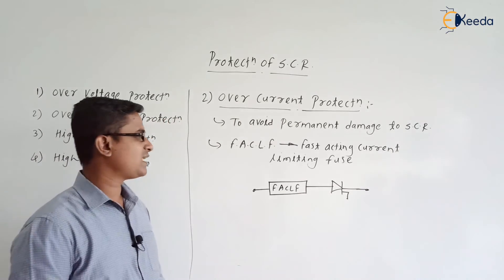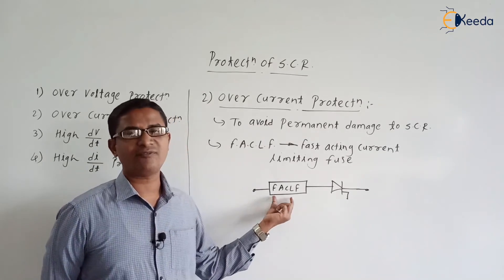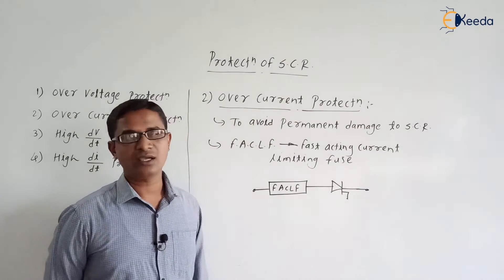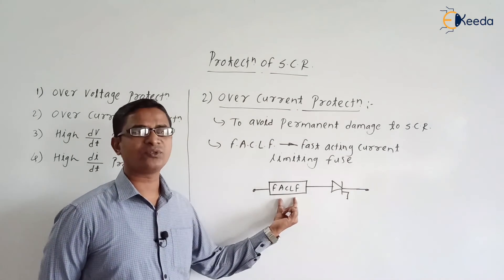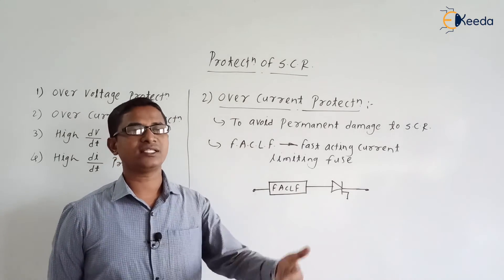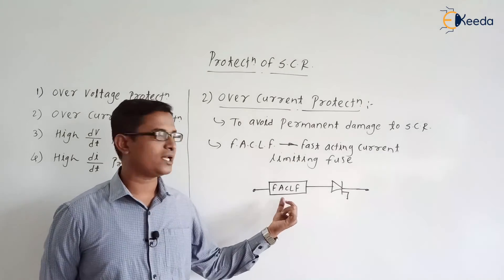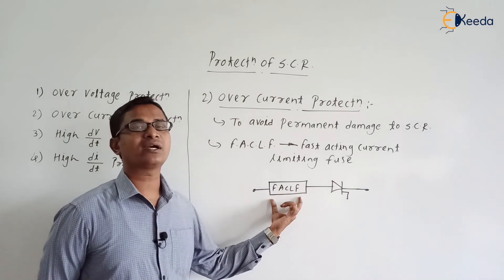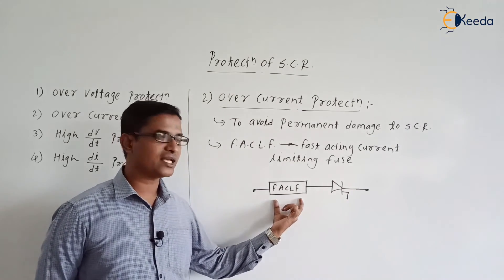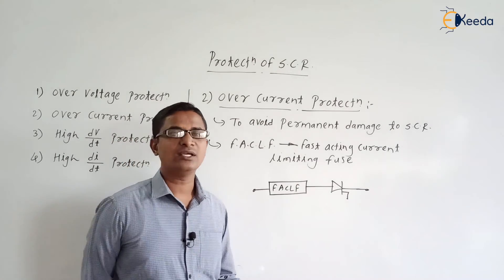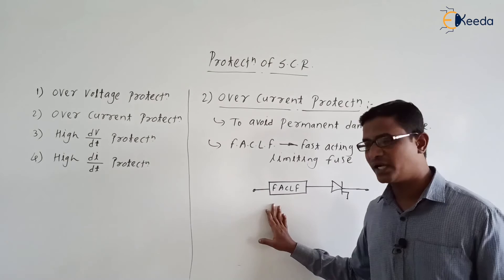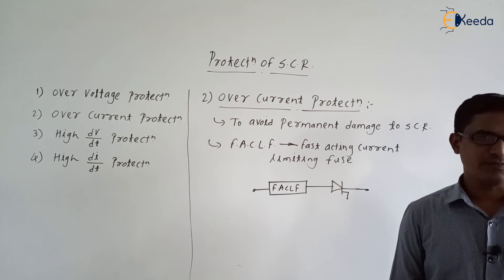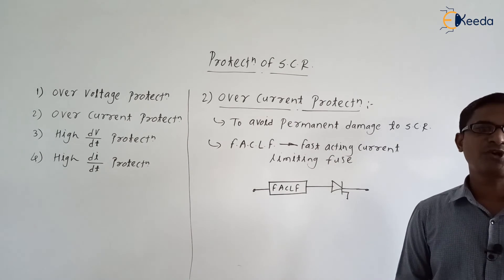The FACLF works like a simple fuse. Every FACLF has a current rating, which should be the same as the current rating of the SCR. When the current flowing through the FACLF increases beyond its rating, the fuse will melt and act as an open circuit. In this way, the FACLF protects the SCR against over current.